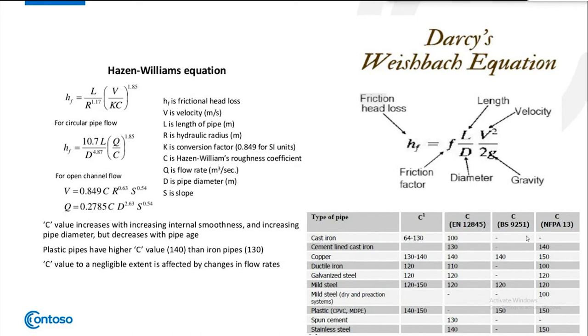For Darcy's Weisbach equation, the formula is HF equals F multiplied by L/D multiplied by V squared over 2G. C value increases with increasing internal smoothness and increasing pipe diameter, but decreases with pipe age. Plastic pipes have a higher C value of 140, compared to iron pipes at 130. C value is affected only to a negligible extent by changes in flow rates.